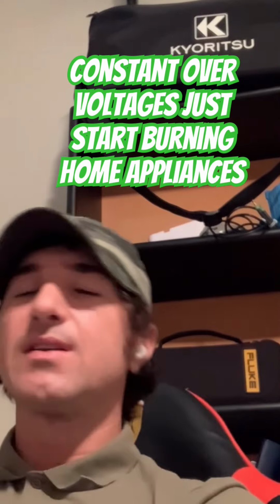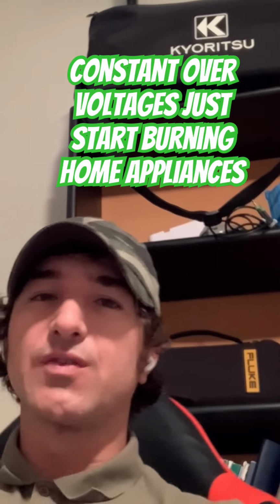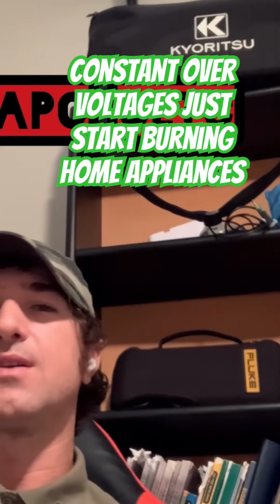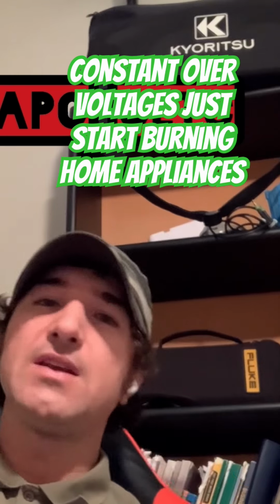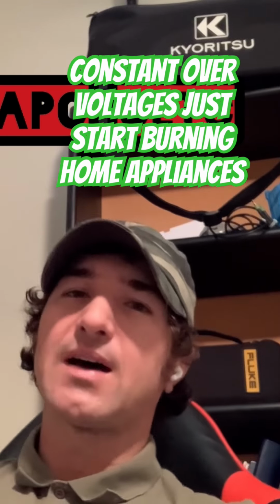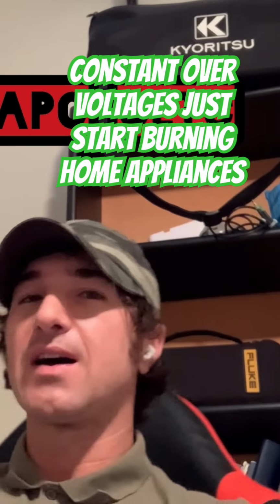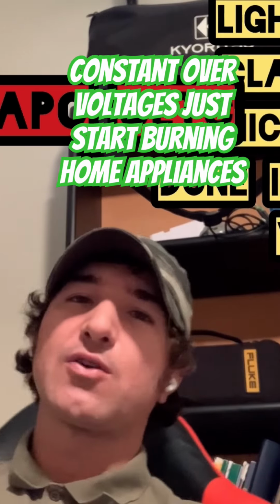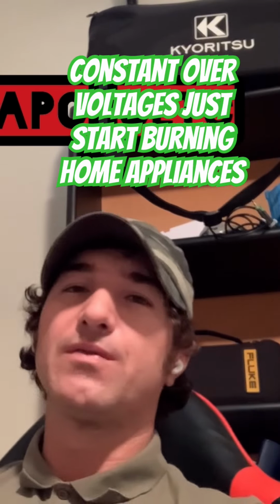There's actually another one: the utility transformers. Tappings can be set too high, and when the current of the feeder drops, like in idling loads, you find excessively high voltages by, like, the first home and stuff. This is very common, especially where there's poor voltage regulation.